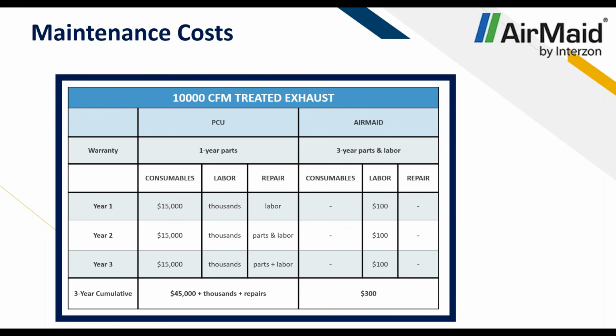So, just looking at a PCU versus AirMaid, especially if you're trying to keep a better system and keep the odors down, we're looking at those comparables. You can see that a PCU is going to cost $15,000 to $20,000 in labor and parts per year just on filters and labor and all that stuff. Whereas the AirMaid is what we call maintenance free, labor free. There's really nothing you need to do. Maybe every year, or every 6 months, just make sure that the cells are still active, and that's pretty much all it is. So it's a very cheap system compared to a PCU.